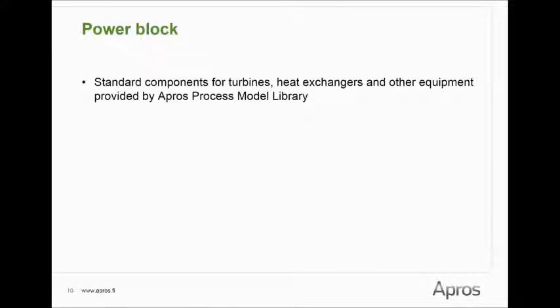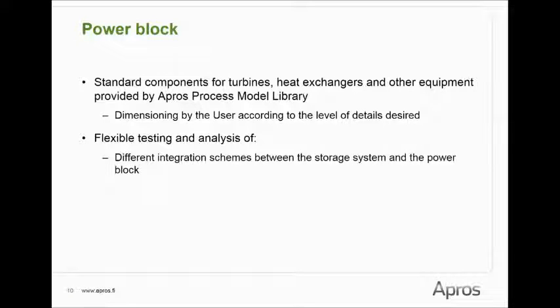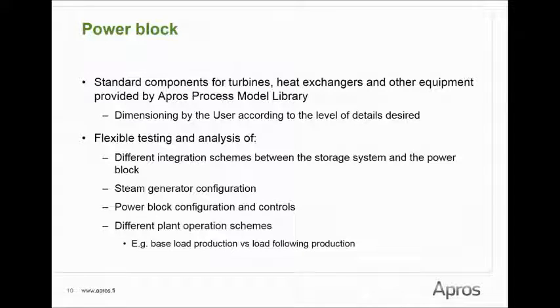The APROS process component model library provides standard components for turbines, heat exchangers and other equipment needed for the heat exchanger train and power block modeling. The inputs of the process component models include the physical dimensions and basic correlations, and these are given according to the level of detail desired in a specific model. The model is a flexible tool for the testing and analysis of different integration schemes between the storage system and the power block, different steam generator configurations, power block configurations and controls, and different plant operation schemes, such as base load production versus load following production.